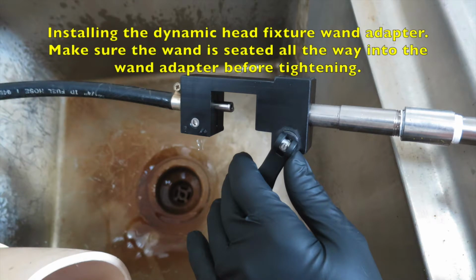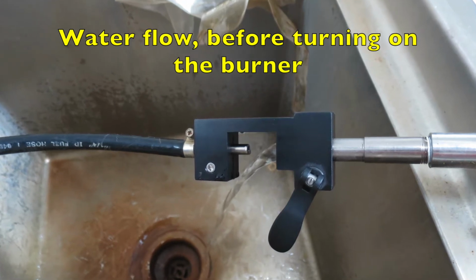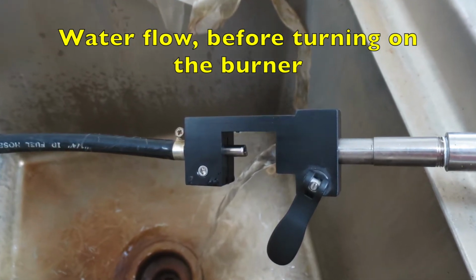Before running a thermal shock test, the thermal shock machine will need to be calibrated. Therefore, before turning the machine on, you will need to install the wand adapter for the dynamic head fixture. This will allow you to check the dynamic head pressure following the warm-up portion that is covered in the warming up the equipment section. You can see how the water flows through the wand with the adapter attached.